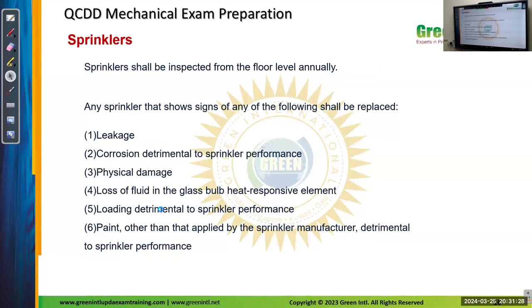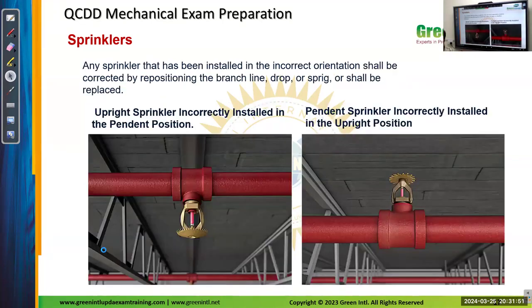Sprinklers shall be inspected from the floor level annually. Any sprinkler that shows a sign of any of these defects, like leakage, corrosion, physical damage, loss of fluid in the glass bulb, or loading of detrimental sprinkler performance paint, if you see any of these defects, you have to replace the sprinklers. So there is a thumb rule.